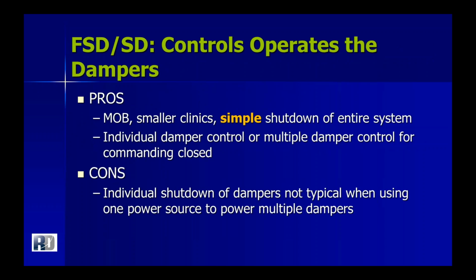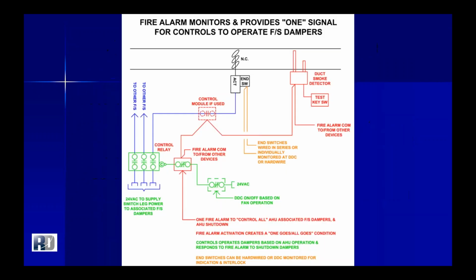So where controls operates the dampers, the pros, where we see this is typically on smaller office buildings, clinics, medical office buildings like we've indicated here. It's a simple shutdown of kind of a one goes, all goes, entire system upon activation. Individual damper controls still can occur, depending on how the control contractor would power these up, because typically the control person would be the one that controls and powers these devices. Also, though, a con can be the reciprocal of a pro, depending on, again, how the control contractor is powering these devices. It might not make it as easy for individual damper control, and where that mainly becomes an issue is when you are doing the annual or every number of year inspection.